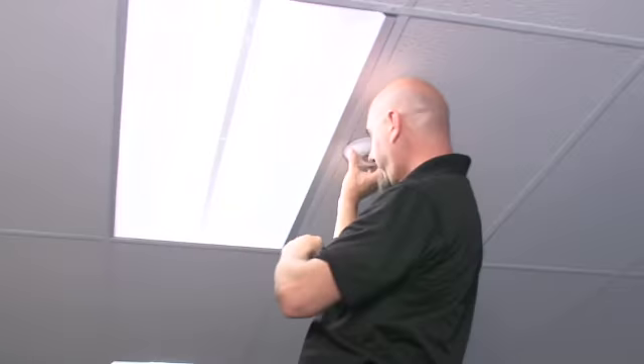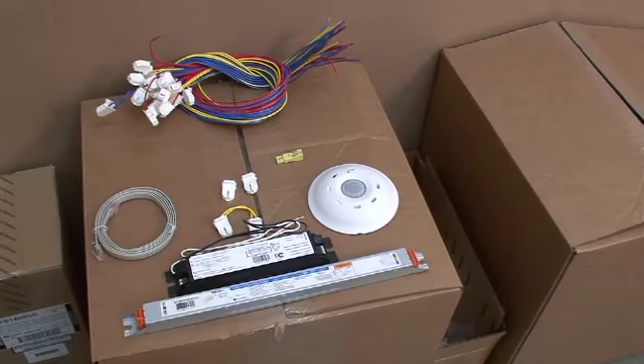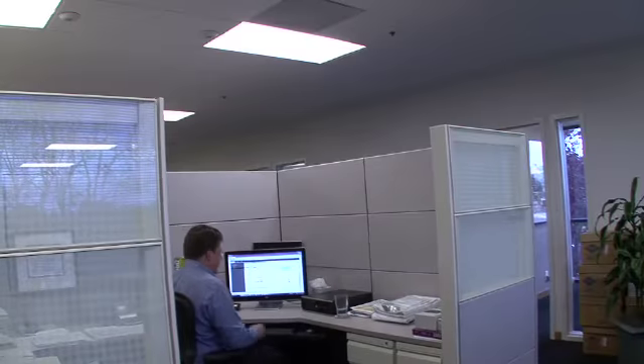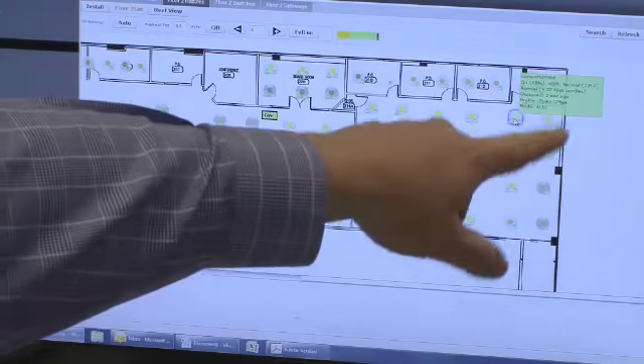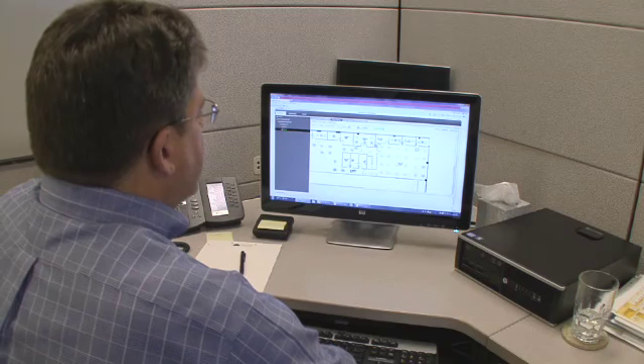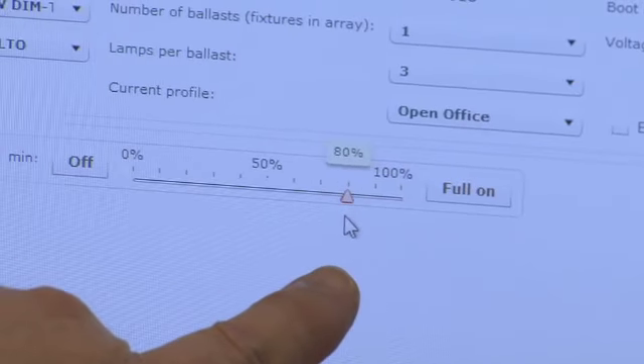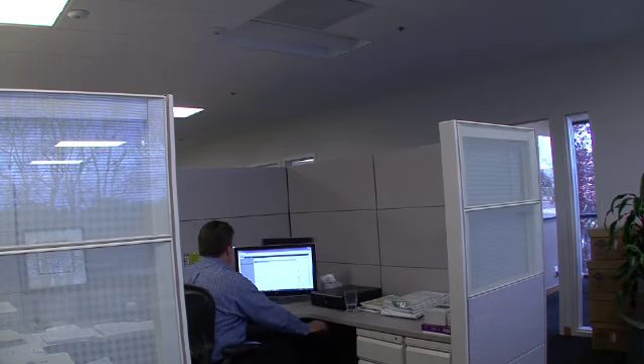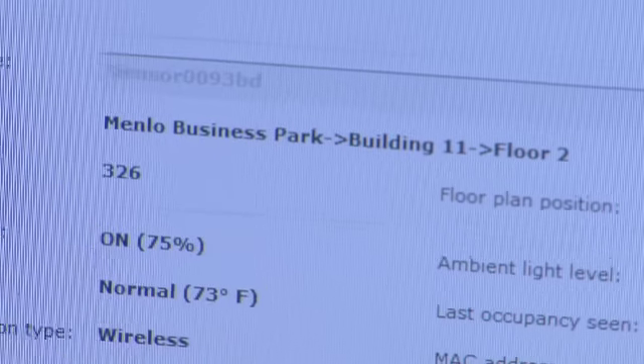The current project utilizes a dimming ballast in all of the fluorescent light fixtures, so that with controls on a cloud-based remote dashboard control system, literally fixture by fixture, you can program a light over an individual workstation or a pair of lights in an individual private office. If we get the message from the PG&E grid management office, we can create an energy reduction for that particular peak demand event.